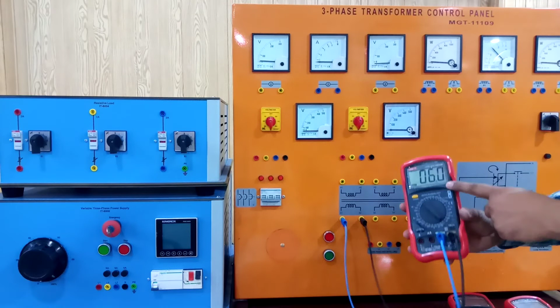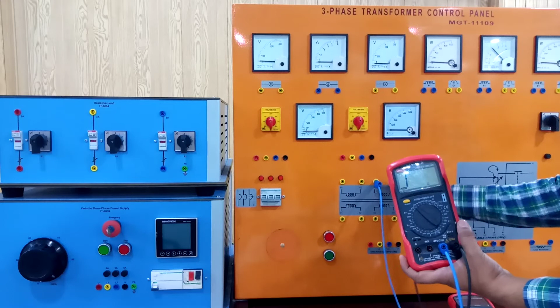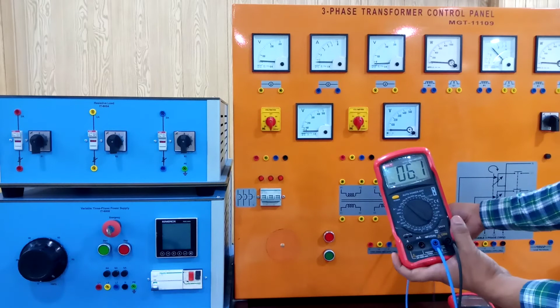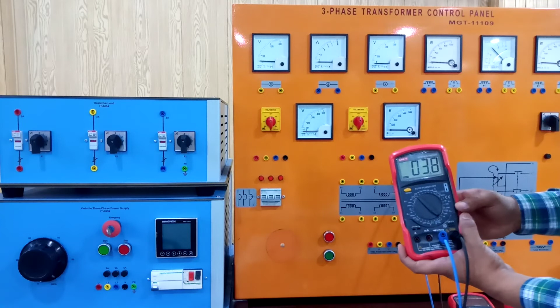Similar for all the other transformers - again this is 6.1 and the other side is 0.6, so this is the low voltage and this is the high voltage. Same for the third transformer - 6.1 and 0.6. So the portion we have here is the high voltage side, which we'll use as the primary, and these terminals are the low voltage side, which we'll use as the secondary.